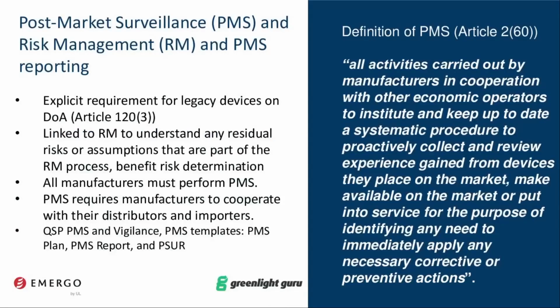So a few comments about post-market surveillance, since it's such a significant aspect of the MDR and of compliance. One comment is that we all realize that there is an explicit requirement for legacy devices on the date of application. So there's no question that even if a manufacturer has a notified body issued MDD certificate, or they have an upclassified product by the MDR, they are required to be compliant to the MDR post-market surveillance provisions. So because on the date of application.